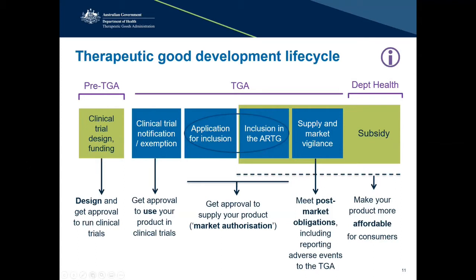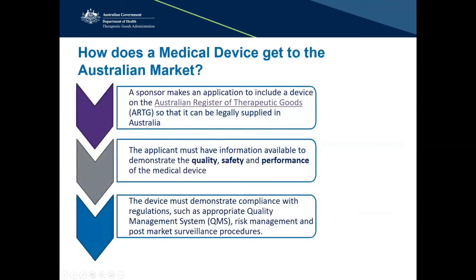In terms of the process, a sponsor will need to lodge an application with the TGA. The application will need to include evidence to show that the manufacturer of the medical device is appropriately certified to manufacture that type of device. And the manufacturer is also required to hold evidence that demonstrates that the device is safe, fit for purpose, and will perform as intended.